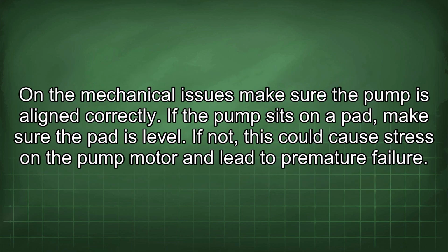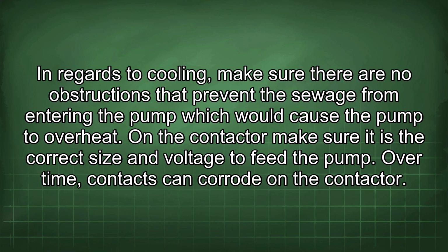On the mechanical issues, make sure the pump is aligned correctly. If the pump sits on a pad, make sure the pad is level. If not, this could cause stress on the pump motor and lead to premature failure. In regards to cooling, make sure there are no obstructions that prevent the sewage from entering the pump, which would cause the pump to overheat.